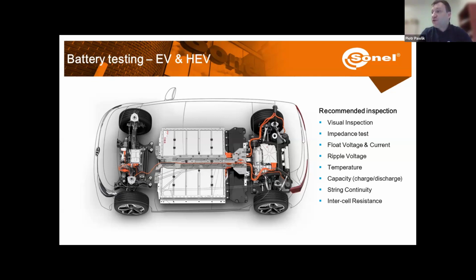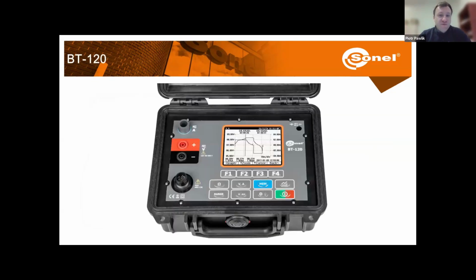We can check temperature, capacity, so charge or discharge test. We can check the continuity of the string of the batteries and the intercell resistance. And for that reason, at Sonel, we have a battery tester called BT 120. So that's the meter that allows you to perform all of these tests.